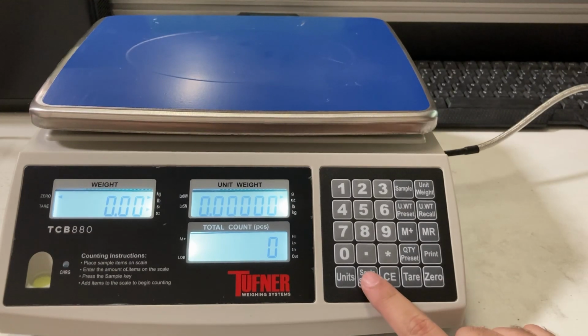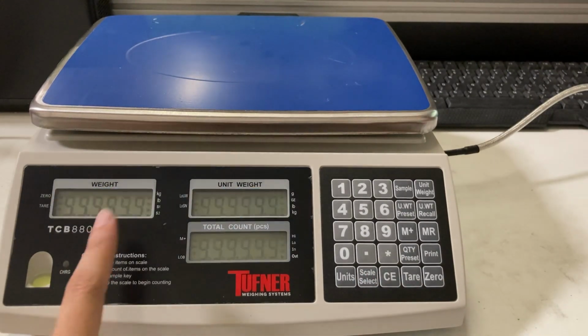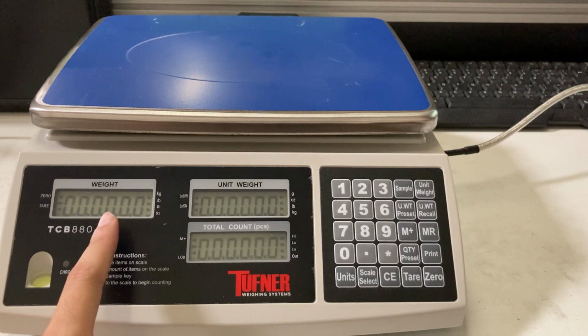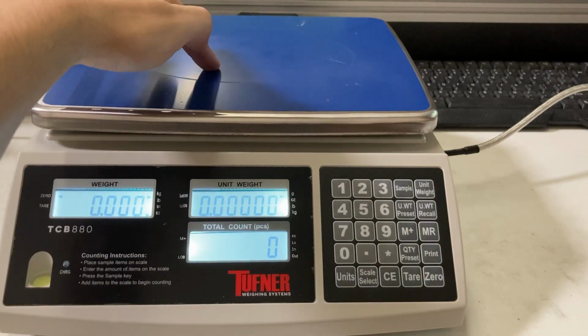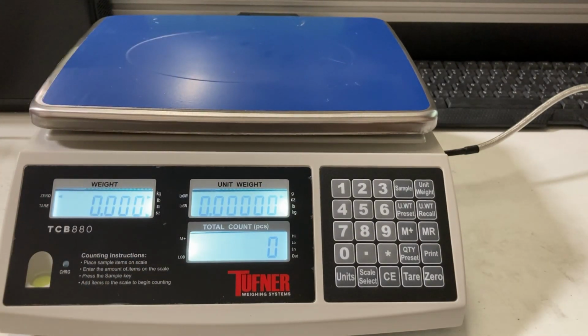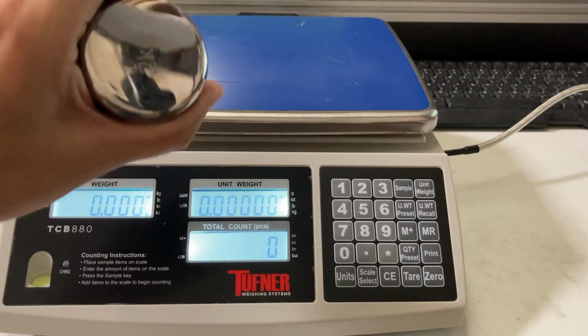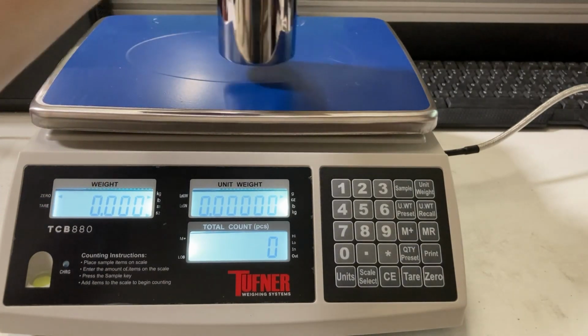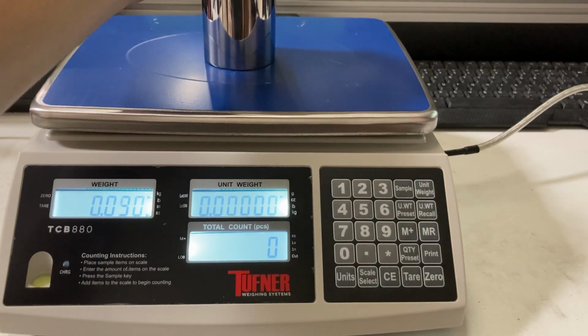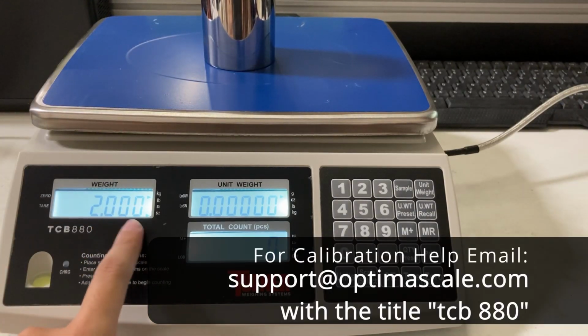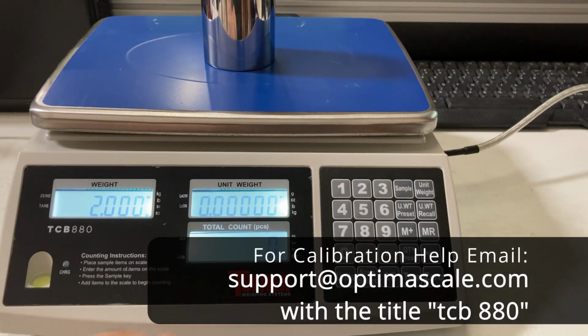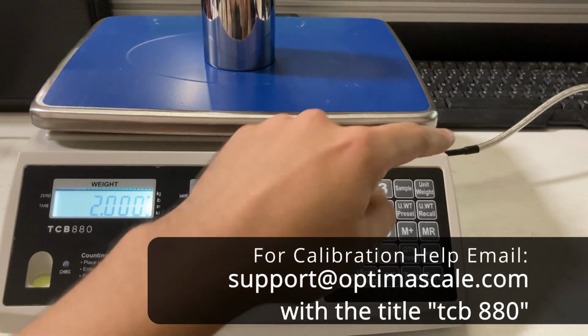And I could do scale select, and it's going to count, and then it's going to start showing the top one. So you can see I'm going to place my 2 kg on here - and again, depending on how good your calibration weight is, that's how good the calibration is going to be. 2 kgs - so if I use a more precise weight, I'll probably get it more accurate on the second external scale, the one connected over there.